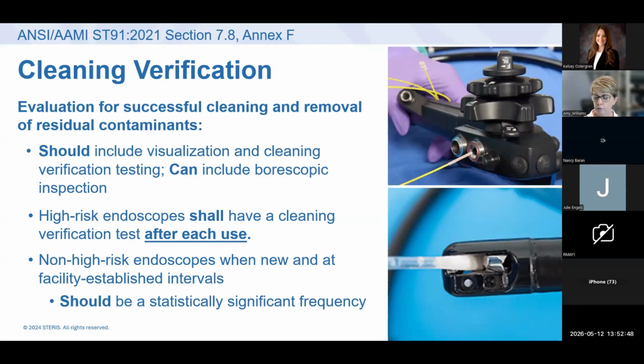And I also point out here too that if you're using one of the OERs that I mentioned a minute ago, where you bypass manual cleaning and you go straight into the reprocessor, my question for you is always, when are you doing cleaning verification testing? ATP, carb, hemoglobin, whatever those tests are, that's meant to be done after manual cleaning to validate that manual cleaning was effective. If you're not doing manual cleaning and you're putting it straight into the OER, when are you doing your cleaning verification testing? Okay. Because if you do it after it comes out of the AER, that's a moot point. Okay. So just think about that.